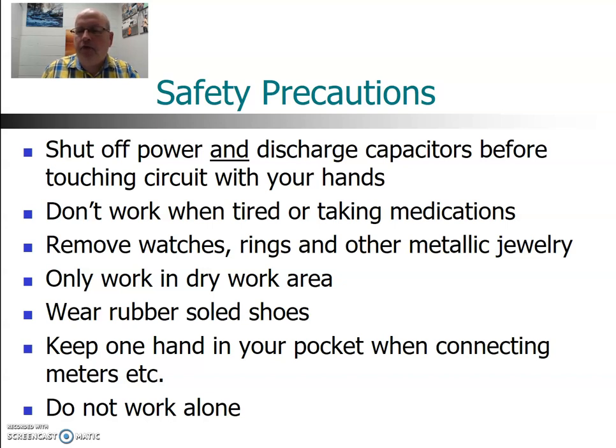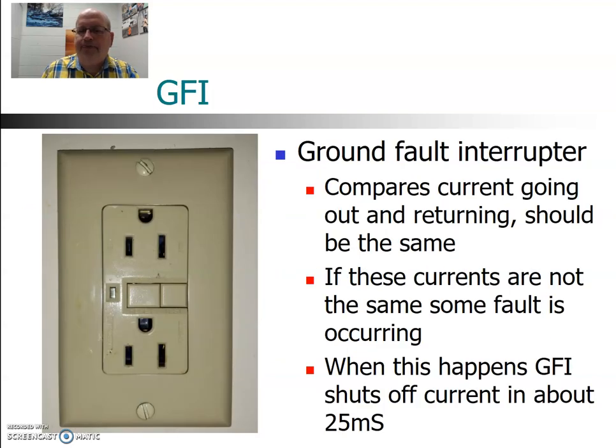Remove any watches, rings, or other metallic jewelry. Work only in a dry area. Wear rubber-soled shoes. Keep one hand in your pocket when connecting a meter—you may look silly, but you don't want a second point of contact, since you're presumably already wearing rubber-soled shoes. Lastly, don't work alone. You need somebody who, if you do get an accidental shock, can shut off the electricity, call for medical help, and so on.